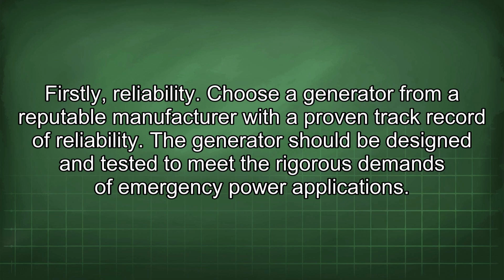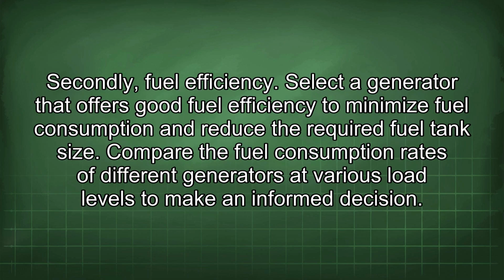Firstly, reliability. Choose a generator from a reputable manufacturer with a proven track record of reliability. The generator should be designed and tested to meet the rigorous demands of emergency power applications. Secondly, fuel efficiency. Select a generator that offers good fuel efficiency to minimize fuel consumption and reduce the required fuel tank size. Compare the fuel consumption rates of different generators at various load levels to make an informed decision.